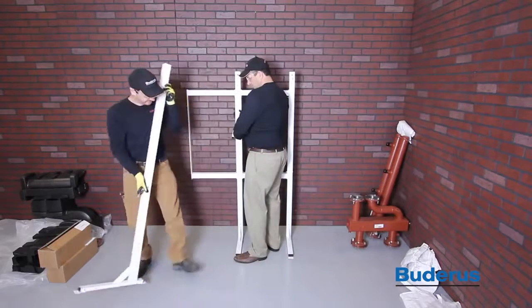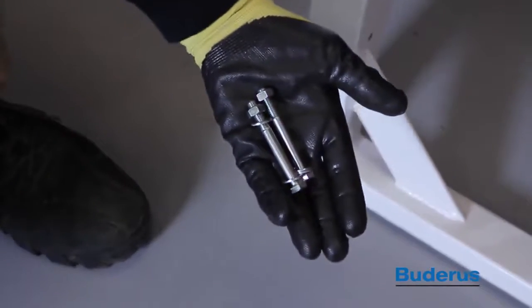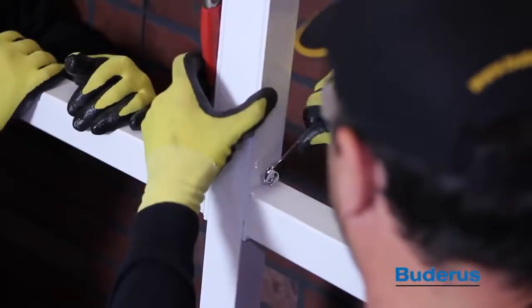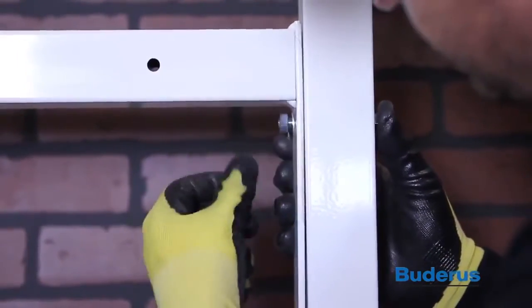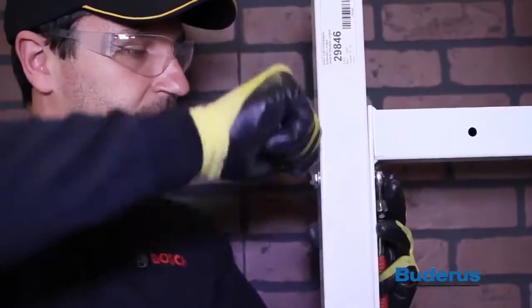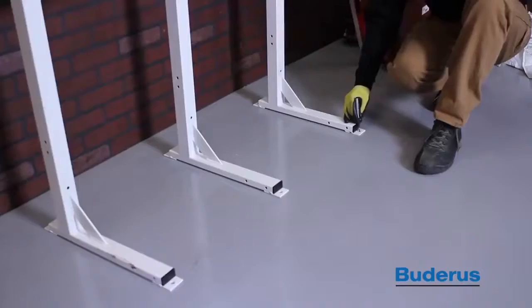The GB162 cascade system utilizes a floor-mounted rack system for hanging the boilers. The rack system must be installed on a flat level surface. Fix the support frame to one upright support using two 8mm by 70mm bolts and nuts provided. Be sure that the pre-drilled holes for the boiler hanging bracket are positioned at the top. Attach the next upright support and frame using the bolts and nuts provided. Attach the last upright support to the support frame using two 8mm by 70mm bolts and nuts provided. Position the assembled cascade frame in its final position, level it both horizontally and vertically, and secure the cascade frame to the floor.